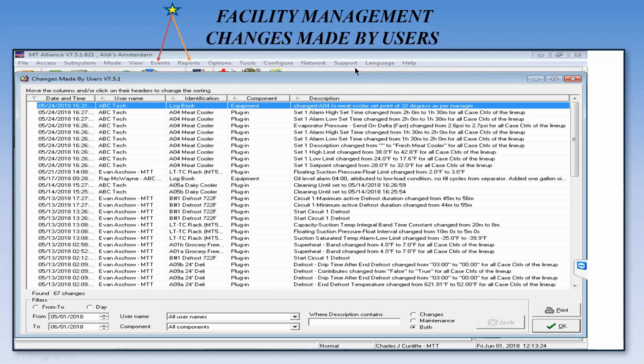The report I'm talking about right now is called Changes Made by Users. For either the end user, the supermarket, or the contractor, this shows you, for 3 to 5 years, every single change made in the system. Did somebody change a superheat setting? Did somebody change a target set point? A temperature set point? Did somebody drop out a compressor? All of that is kept in the system for you to investigate.